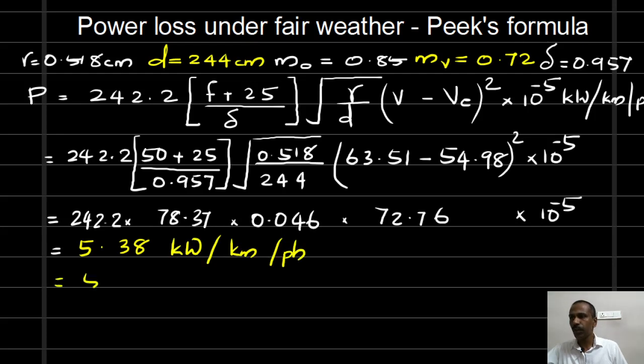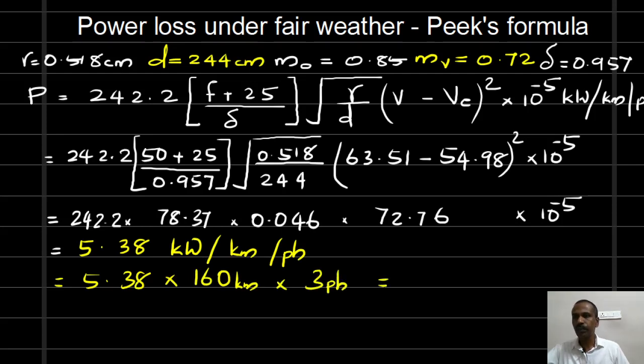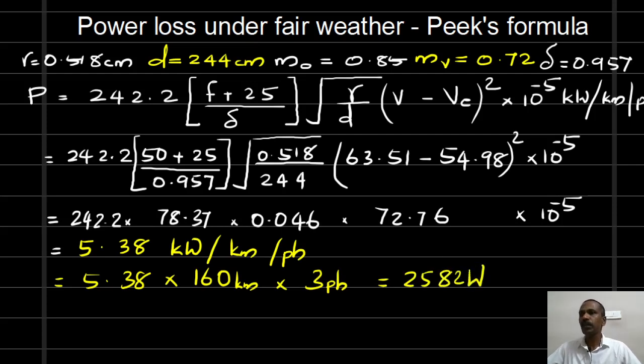The total corona loss for the good weather condition is 5.38 kilowatt per kilometer per phase, multiplied by the line length of 160 kilometers and 3 phases, giving a total of 2582 kilowatt. This is the power loss due to corona formation under the fair weather condition.